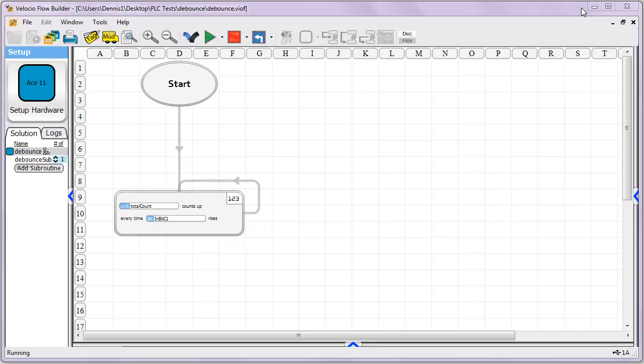It's very, very quickly done, but our PLCs in a typical application will run around 5,000 scans per second. So they run fast enough that they will frequently catch these very rapid transitions. So you want to sometimes slow down the process a little bit for particular inputs. You wouldn't want to do this for all your bits, but just your input bits may sometimes require this to kind of filter out those mechanical bounces. So I'll show you an example here.